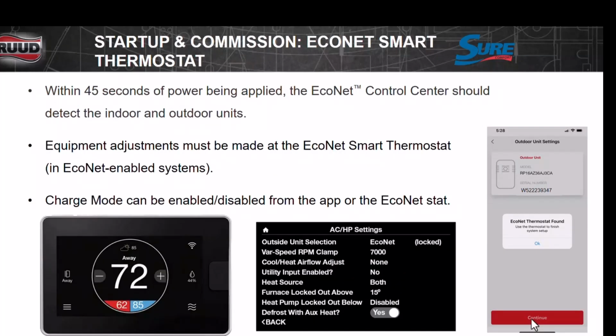Within 45 seconds of power being applied to the EcoNet controller, it will detect the indoor and outdoor units. It's always a good idea to turn the outdoor unit on first on an inverter system, especially the mid-tier, because if you apply power to the thermostat before applying power outside, you will get a code that says it can't find the outdoor fan motor. That's because the inverter is not on. You don't have power to it. In order to cure that, you would go to your EcoNet thermostat and reset the defaults in it and shut it down, pull it off the wall, then go turn the outdoor power on, the indoor power on, and then plug the thermostat in. In that sequence. That way we're assured that everything's powered up by the time we plug that thermostat on. And it'll see that unit. So just keep that in your mind if that happens, because that's not in the presentation.